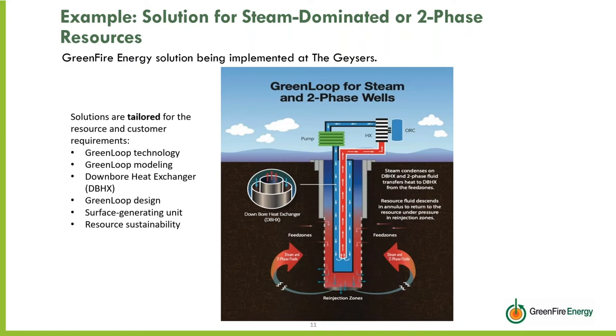Good question. We do, because we control the working fluid 100%, it's in a closed loop. We control the chemistry and we control the temperature, and the temperature is mostly controlled by the speed of the flow of the working fluid. The faster you flow the fluid, the cooler the outside of the downhole heat exchanger will be. And that sets the saturation temperature and saturation pressure within the well so that it actually attracts the steam, in this case, or the two-phase fluid into the resource and causes the condensation to occur.